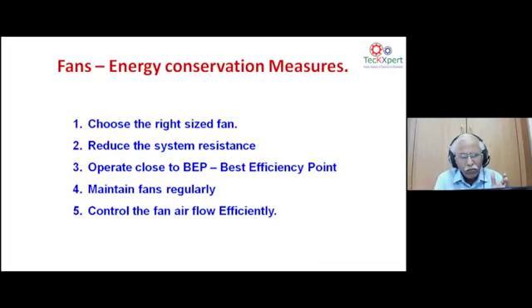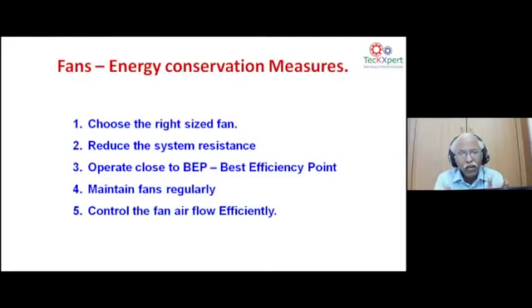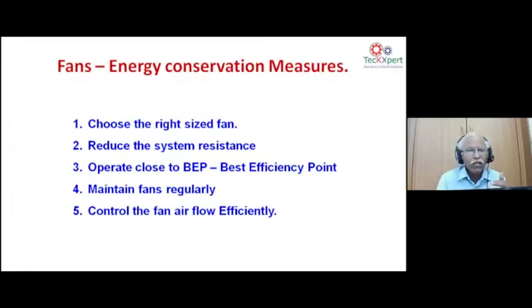The fan performance curve from the OEM shows the best efficiency operating point for the given specifications. We should operate the blower at that best operating point. Fourth is regular mechanical and air-side maintenance. Fifth is efficient airflow control — through VFD, damper, or inlet guide vanes — with an understanding of what each method delivers and what losses each introduces to the system.